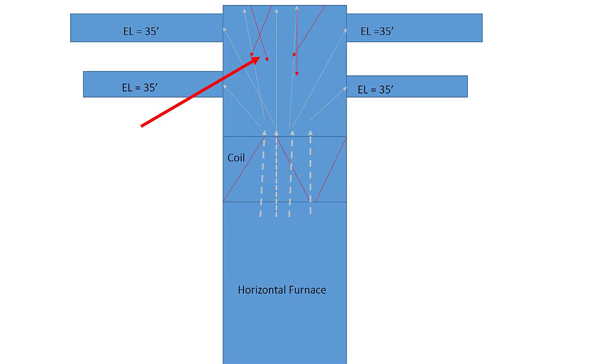This means that before we even get out of the box, we've got 140 equivalent length feet on this furnace. We also have a lot of turbulence. The air coming out of the box, out of the coil, is bouncing around in the box and causing a lot of turbulence before it gets into the ductwork. And you also have restricted airflow across the coil.